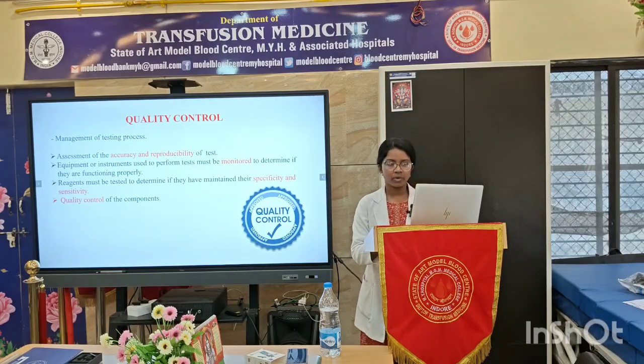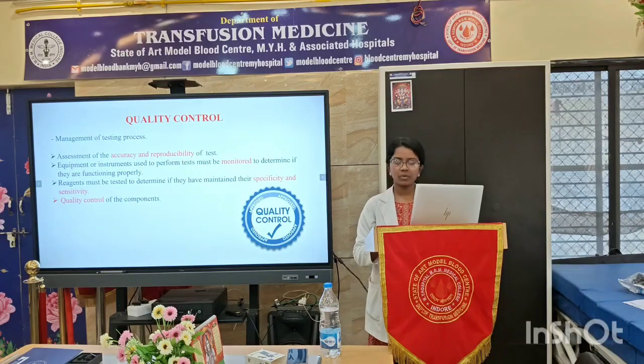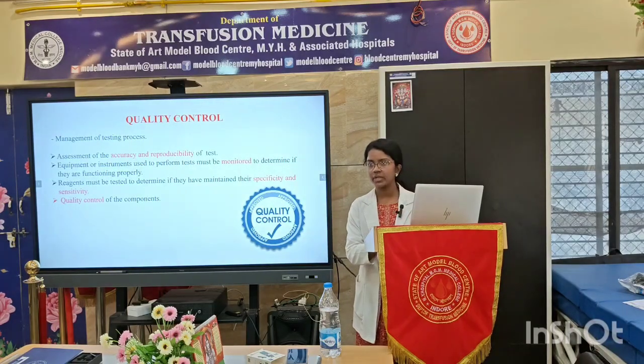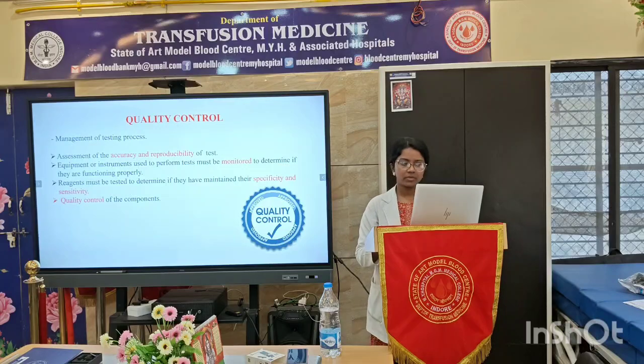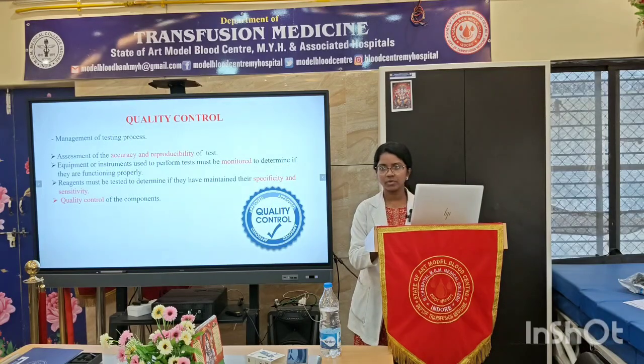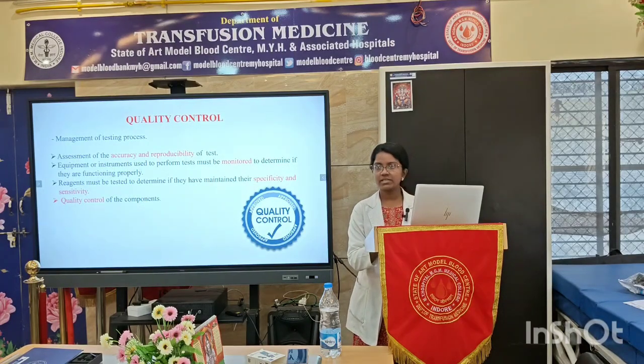Before going into the topic proper, I want to give an overview about quality control and TTI and what we are doing in our department. Quality control is management of the testing process. It includes assessment of the accuracy and reproducibility of a test. Equipment or instruments used to perform tests must be monitored to determine if they are functioning properly. Reagents must be tested to determine if they have maintained their specificity and sensitivity. It also includes quality control of the components which we make.